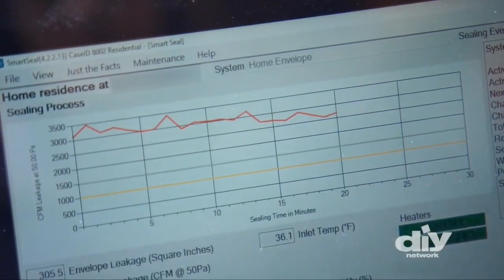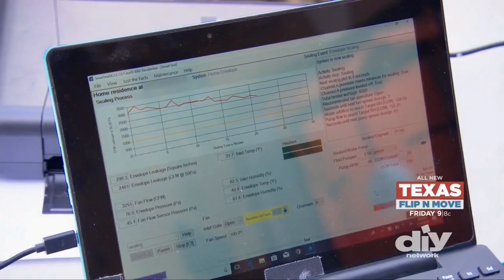We sprayed a product into the suburban home that will seal almost all the cracks and holes where there is air leakage. Right now you're at 305.5 square inches of leaks — that's a lot of leakage. As this graph goes down, that just means that the house is getting more airtight. It's sealing the holes, and it'll continue dropping.